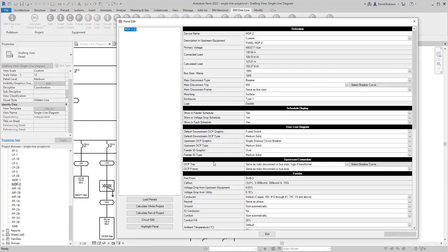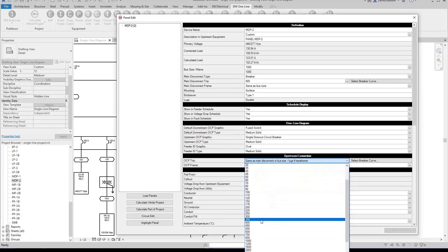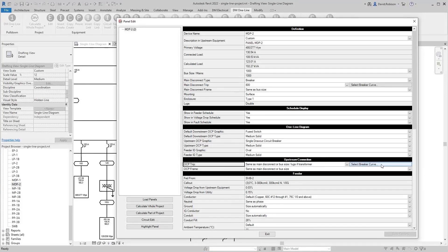The upstream connection section sets the overcurrent protection trip size and corresponding frame size. By default it matches the main disconnect size. If connected to a transformer, we assume no overcurrent protection and leave it as lugs. You can override this to add a breaker for a transformer connection, set it to always be lugs, or specify a specific breaker size. You can also select the breaker curve for the overcurrent protection breaker in the upstream panel.